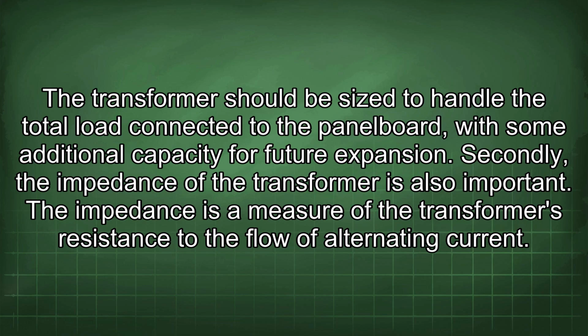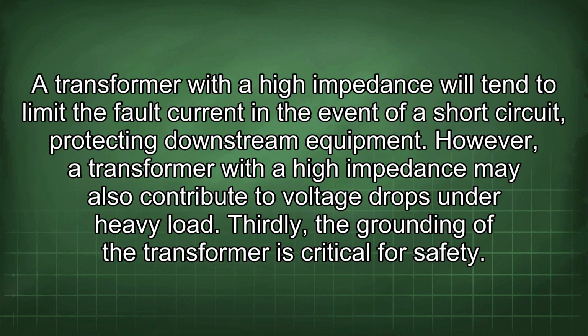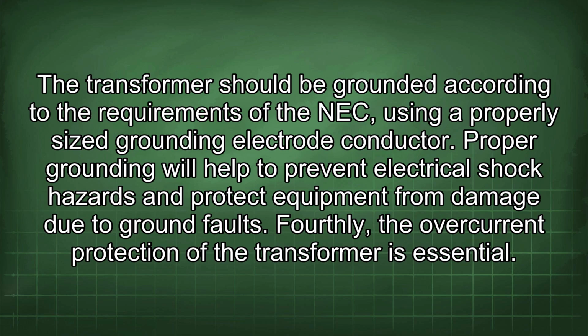Secondly, the impedance of the transformer is also important. The impedance is a measure of the transformer's resistance to the flow of alternating current. A transformer with a high impedance will tend to limit the fault current in the event of a short circuit, protecting downstream equipment. However, a transformer with a high impedance may also contribute to voltage drops under heavy load. Thirdly, the grounding of the transformer is critical for safety. The transformer should be grounded according to the requirements of the NEC, using a properly sized grounding electrode conductor. Proper grounding will help to prevent electrical shock hazards and protect equipment from damage due to ground faults.